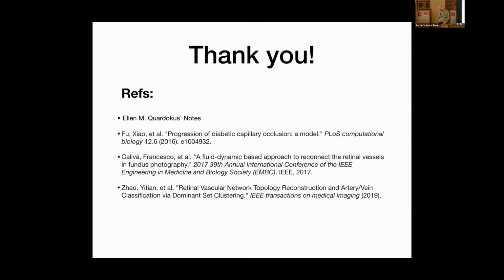It's not a trivial modification from the point of view of the FDA, but it's a trivial modification technically. So if you had a computational method that said, instead of ablating in a grid or a random pattern, that you should ablate in particular regions, that could be a software patch to an existing machine.